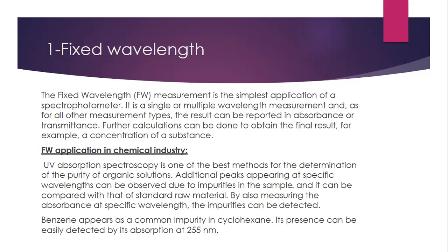The first application comes under fixed wavelength. Fixed wavelength measurement is the simplest application of a spectrometer. It is a single or multiple wavelength measurement, and as for all other measurement types, the result can be reported in absorbance or transmittance. Further calculations can be done to obtain the final result, for example, the concentration of a substance.